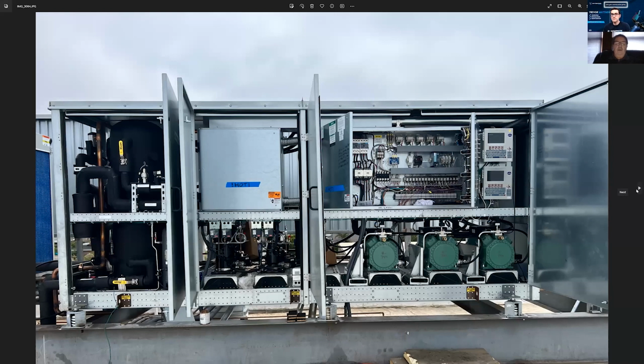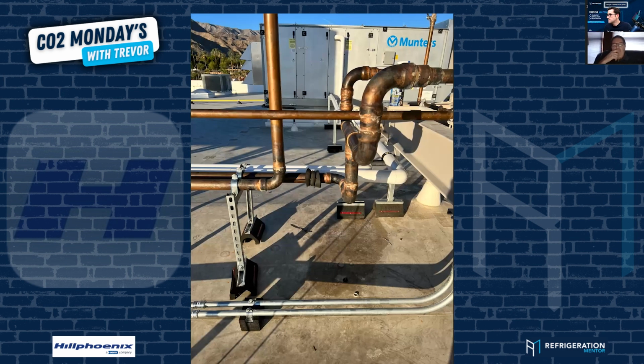Well, on our oil system, it's like that because... Did I send you any pictures of the oil system of the HPSO 1 or 2 sensors? No, but we've talked about it before. Yeah, how it works is we've got a sensor that sits horizontally in our receiver, our separator, and our vessel. They work off conductivity. There's an isolated probe in the center of the well. There's a well, and then there's a power head. That well is isolated on the inside so that you have your positive, and your ground is the outside. So your fluid is your actual switch.